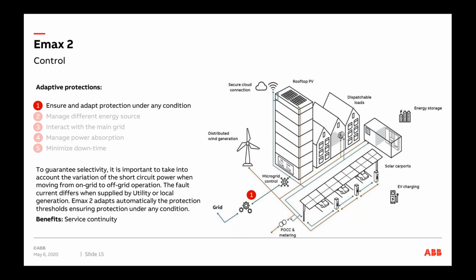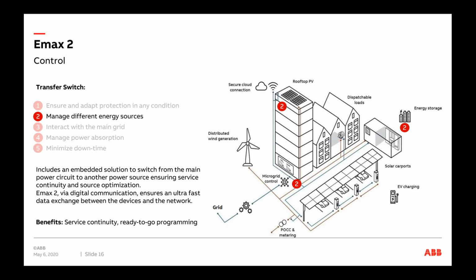Now, this is not a protection feature. It's more to reduce any kind of effect. It's not an elimination, but a reduction of any kind of fault that we could have on site. But it's an option with the breaker itself. So the combination of reduction and protection together makes the whole system safe. So that's adaptive protections.